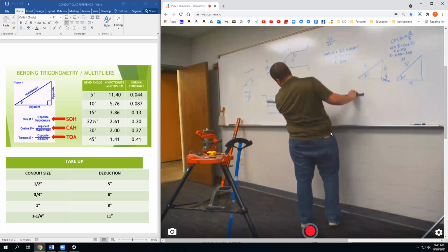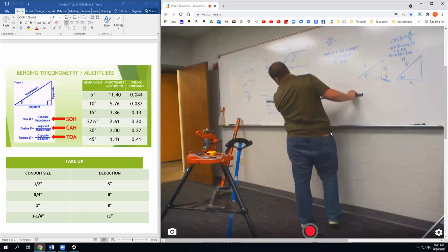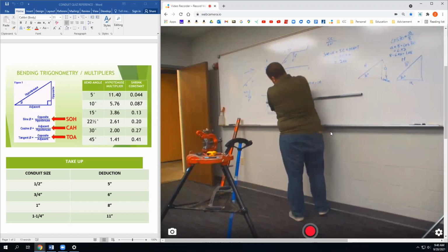So it looks like, to fix this, you bend up your box offset instead of trying to change that angle. If I take this one here and bend it up just a little bit more, put just a little bit more bend into that, which is my floor bend, that would fix it.